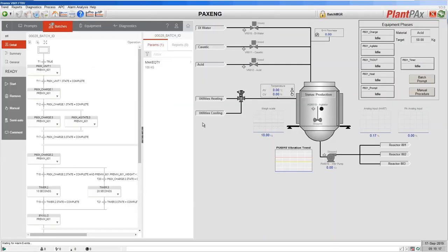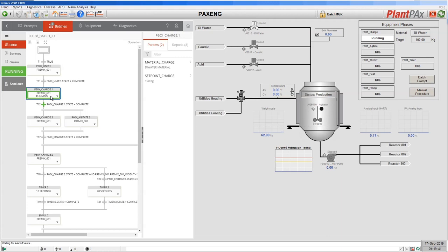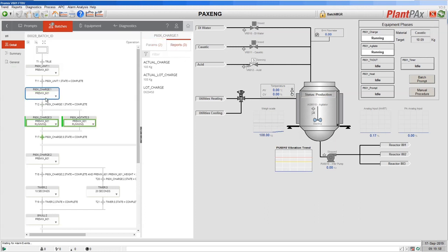Let's now run our recipe from FactoryTalk View. We go back to our graphic and select start, and we'll watch this recipe run through the plant. We're now on the charge step of our recipe. The FactoryTalk Batch operator interface shows us that we're now in the charge step highlighted in green. The valve for water has opened and the charge equipment phase is now charging that DI water into the premixer. If we look at the reports for this step we can see that when the equipment phase completed it reported these values back to FactoryTalk Batch, which has recorded them.